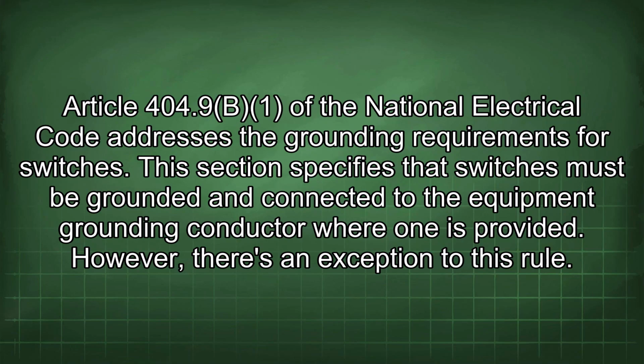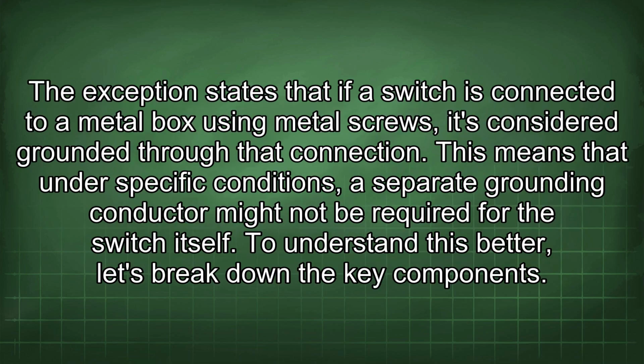Article 404.9 of the National Electrical Code addresses the grounding requirements for switches. This section specifies that switches must be grounded and connected to the equipment grounding conductor where one is provided. However, there is an exception to this rule. The exception states that if a switch is connected to a metal box using metal screws, it's considered grounded through that connection. This means that under specific conditions, a separate grounding conductor might not be required for the switch itself.